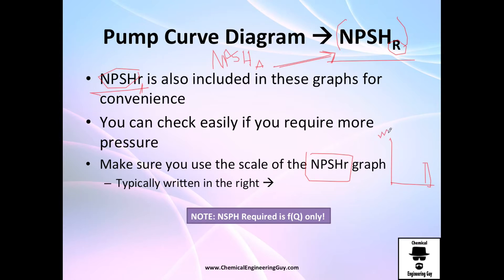Even though we have to the left the head in meters, the NPSH R results in meters, so just be sure to go to the right. It's almost always to the right. One little note: NPSH requirement is function of Q. The more we increase Q, the more NPSH R we need.